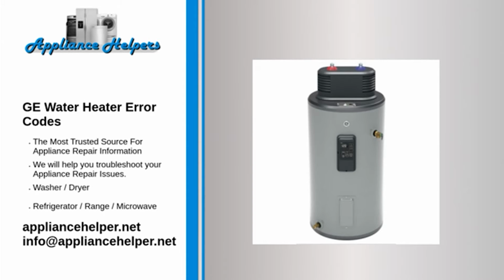Code F2. Problem: tank temperature sensor failure. Fix: the control checks the T2 tank sensor temperature before the compressor starts and it must be 30 to 170 degrees Fahrenheit. Disconnect power or unplug the water heater and then check T2 sensor mounting, wiring, and ohm resistance. Code F3. Problem: compressor failure. Fix: the control energized the compressor but the current sensor does not detect any current flow. Disconnect power or unplug the water heater and then check the compressor, relay, and wiring.